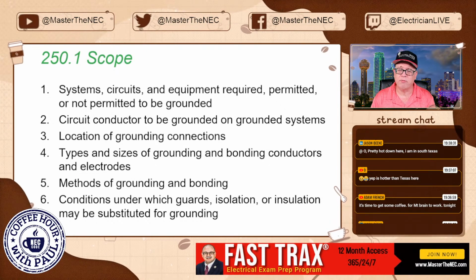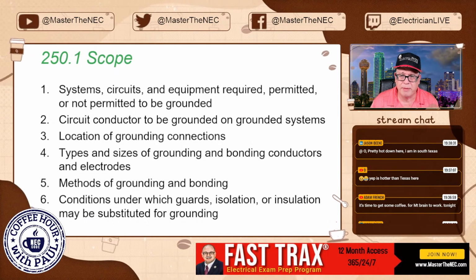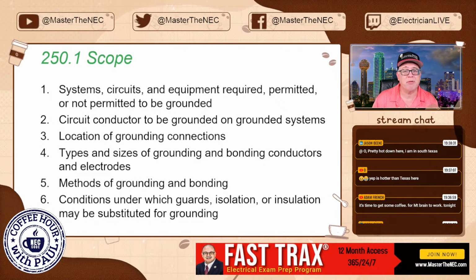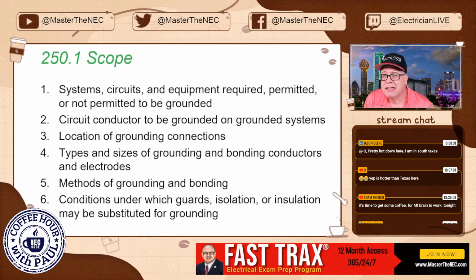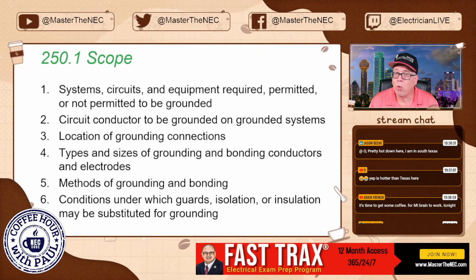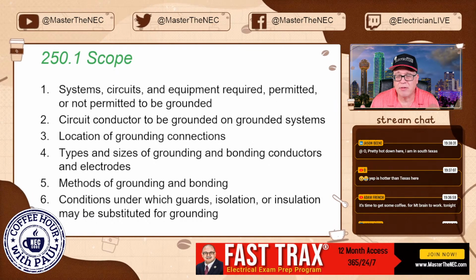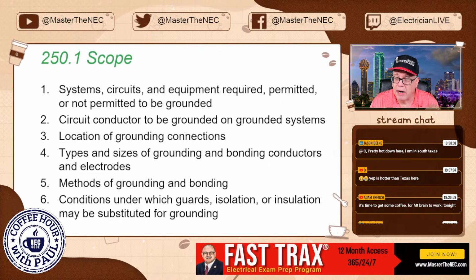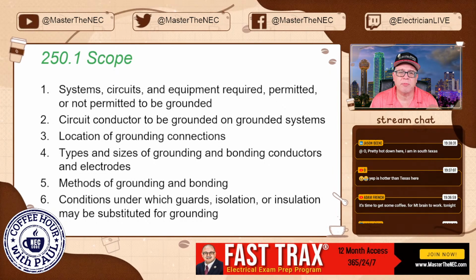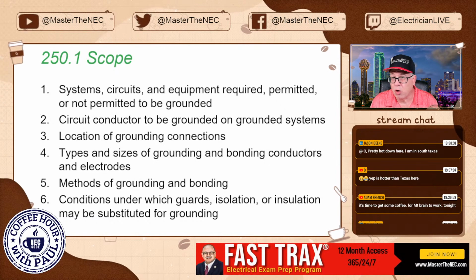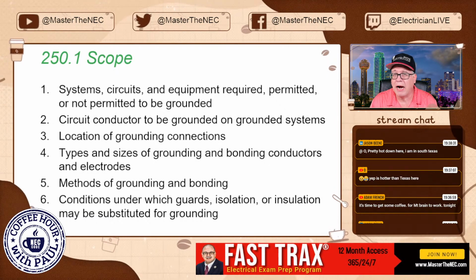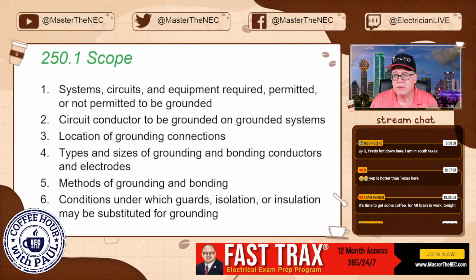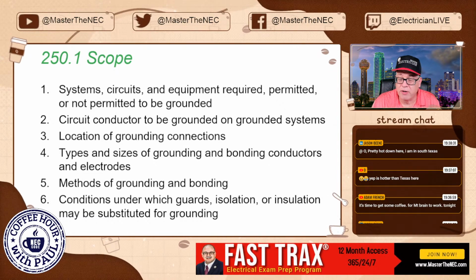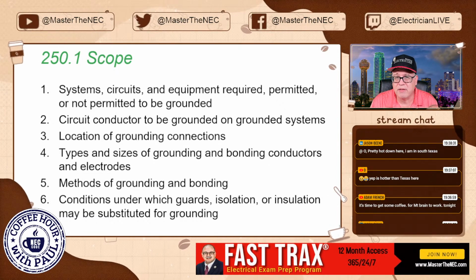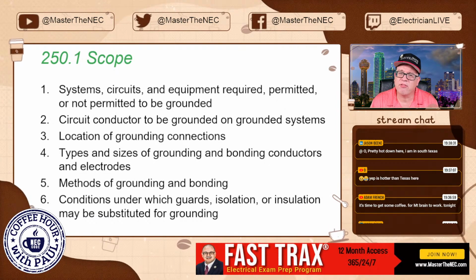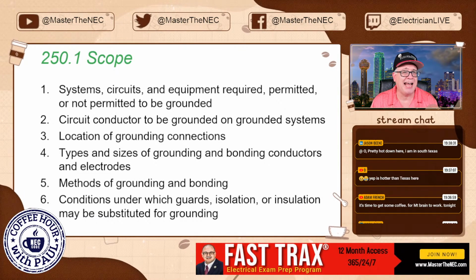So the scope of what 250 covers is systems, circuits, and equipment that are required, permitted, and not permitted to be grounded. Did you actually know that some systems are required to be grounded? Probably the system you have coming into your house is required to be grounded. But you have other systems that are even permitted to be grounded, like a corner grounded delta. It's not required, but it's permitted to do so. And they've got their own characteristics you have to be very aware of when you're dealing with a corner grounded delta. And of course, you have systems that are not permitted to be grounded at all.